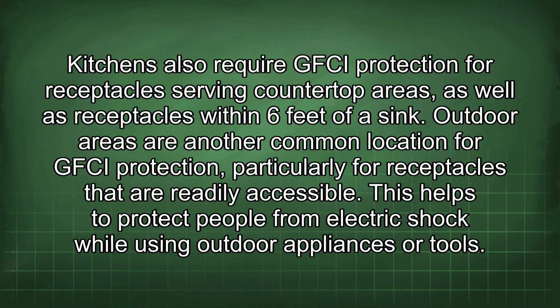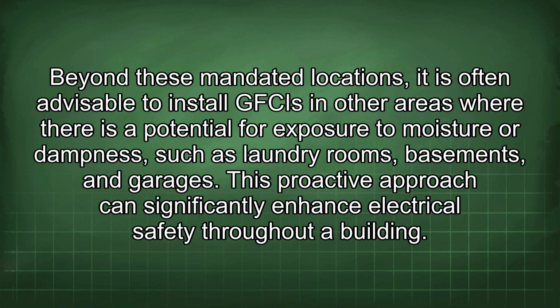Outdoor areas are another common location for GFCI protection, particularly for receptacles that are readily accessible. This helps to protect people from electric shock while using outdoor appliances or tools. Beyond these mandated locations, it is often advisable to install GFCIs in other areas where there is a potential for exposure to moisture or dampness, such as laundry rooms, basements, and garages. This proactive approach can significantly enhance electrical safety throughout a building.